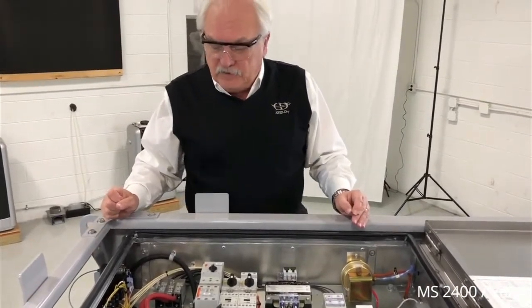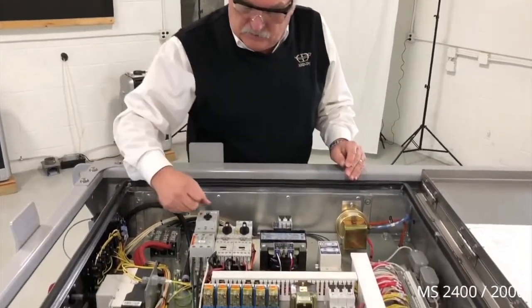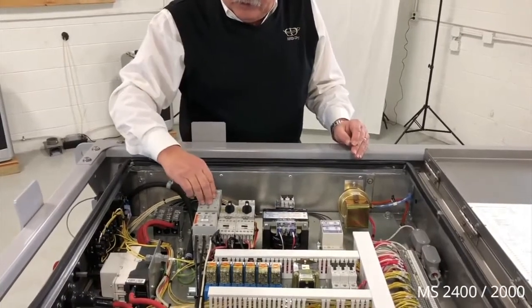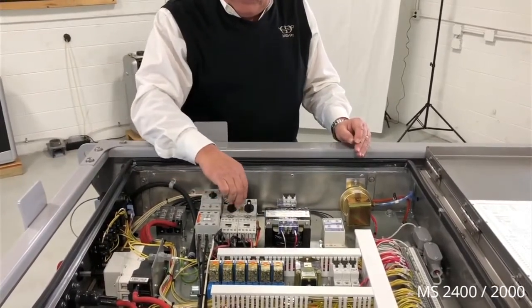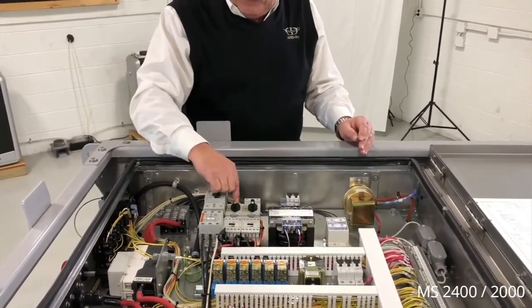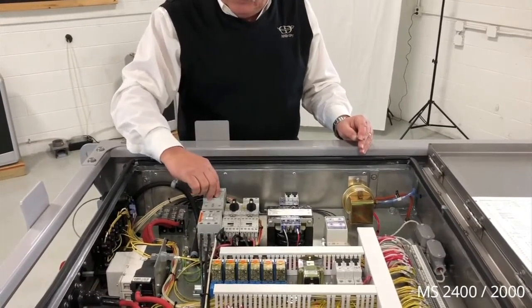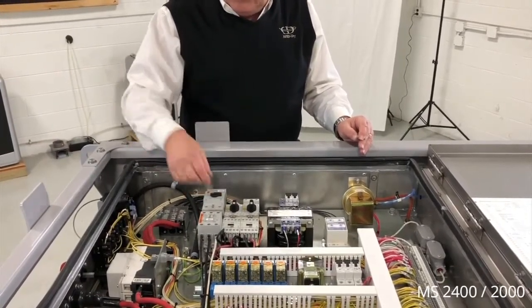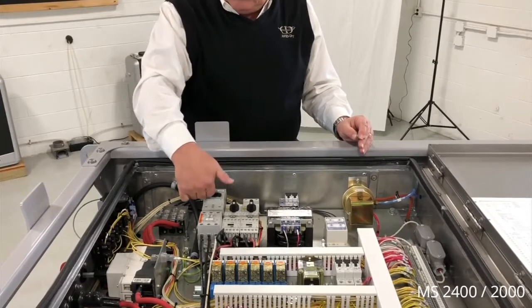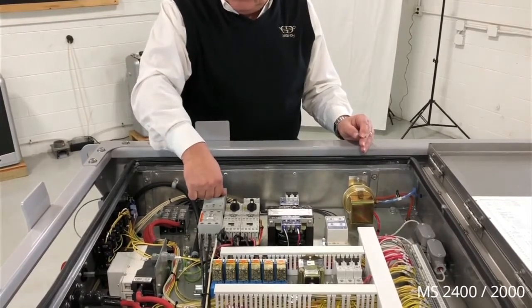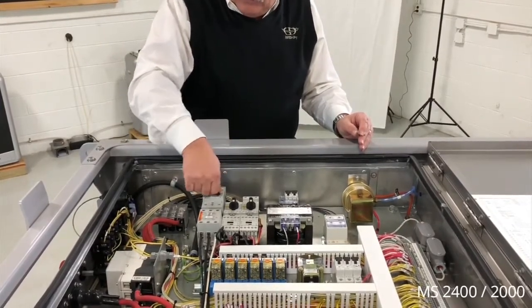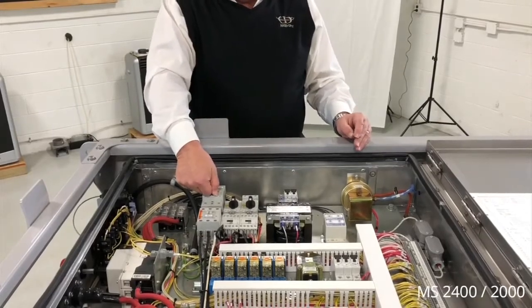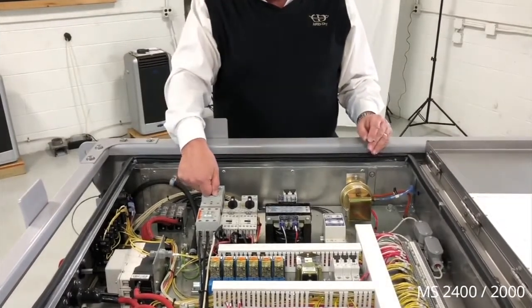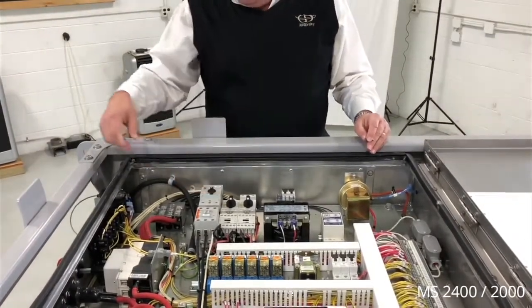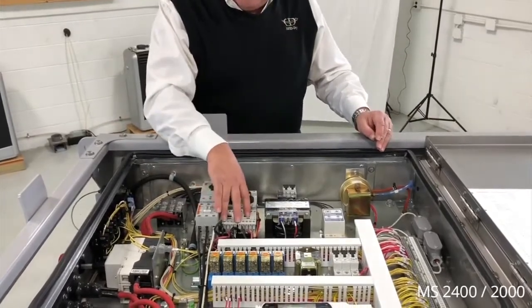The circuit breakers are here for the heater system and for the motor starters. These should be checked to make sure they're in the vertical position. If they are popped, you'll see the circuit breaker in about the 2/3 to 3/4 position. It needs to be cycled all the way back and then cycled back on to bring the unit back into operation. The starters are here.